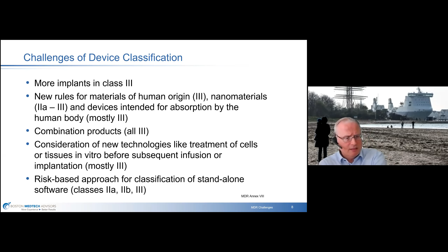Combination products, so a fixed combination of a device and a drug, is typically class 3 now. New technologies like treatment of cells or tissues in vitro before subsequent infusion or implantation, for instance, in stem cell transplantation, these are now mostly class 3 or a combination of multiple devices ranging from class 2A all the way through class 3. And now in the age of digital health, it's interesting to see the classification of software. Standalone software is always an active medical device of class 2A minimum, but depending on the actual risk, it may be class 2B or even class 3. So with medical software, you may end up in a clinical pivotal trial.